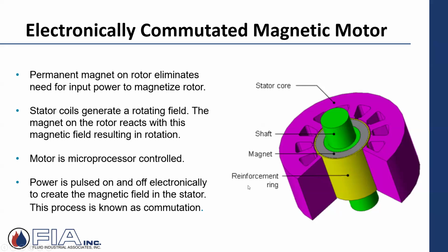So real quickly, electronically commutated magnetic, ECM. That's all it stands for, the 3 letters. Permanent magnet on the rotor, these magnets here, eliminates the need for input power to magnetize the rotor. The magnet's already there. It's attached to the rotor. The motor is microprocessor controlled. Hence, you'll hear the expression smart pumps. So they have some intelligence on board. And then the last part here is this: power is pulsed on and off electronically. Electronically commutated. So as it's pulsed on and off electronically to create the magnetic field, the process is called commutation. Electronically commutated magnetic motor.